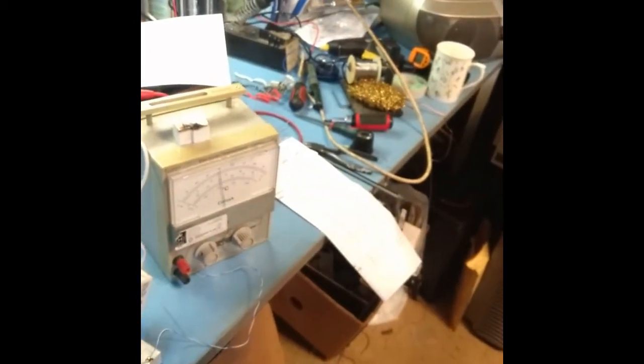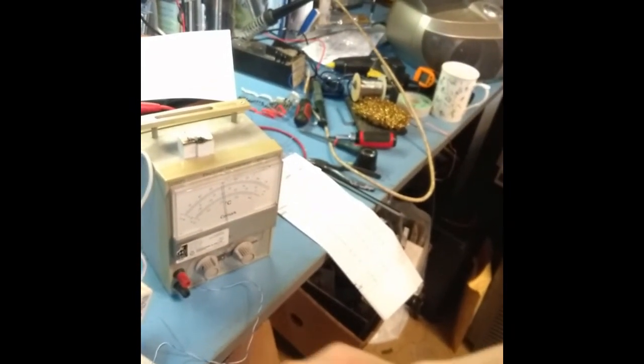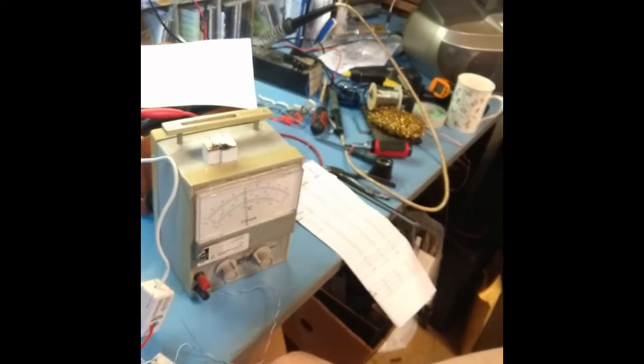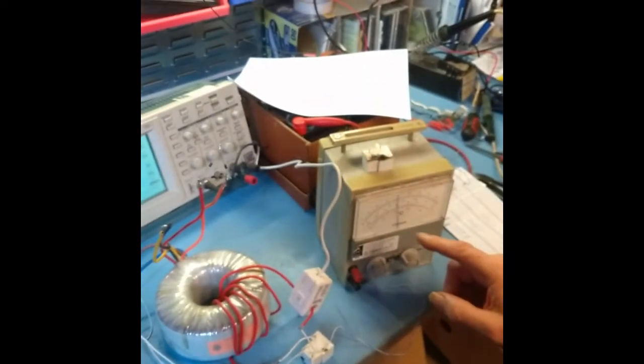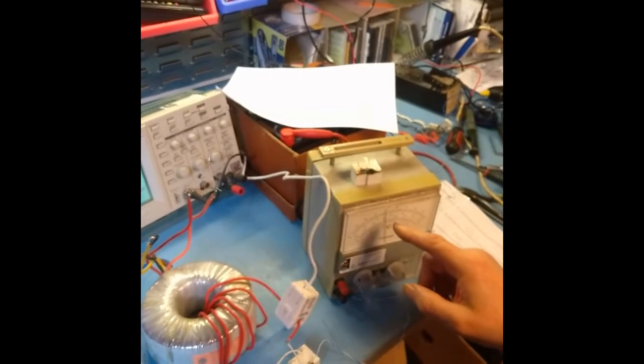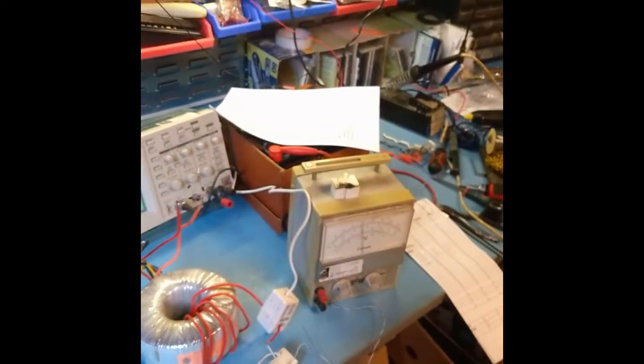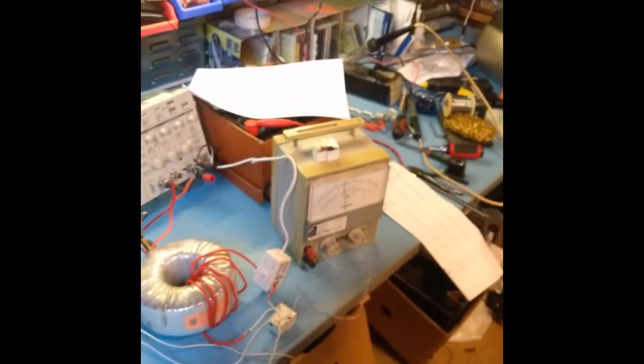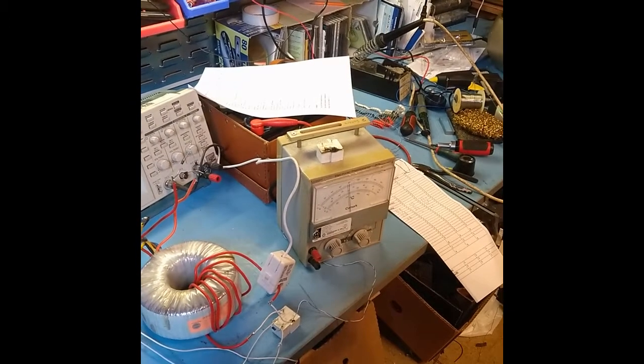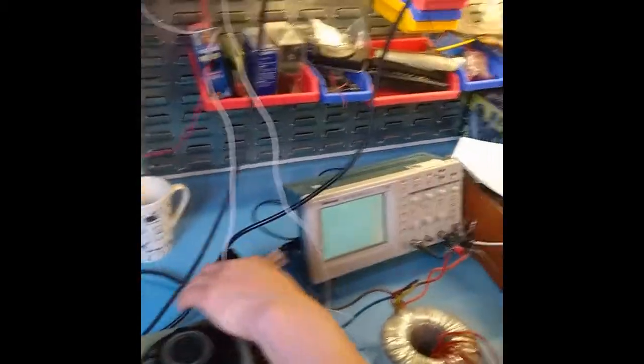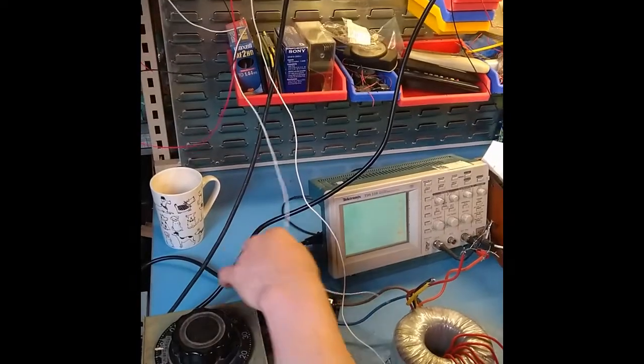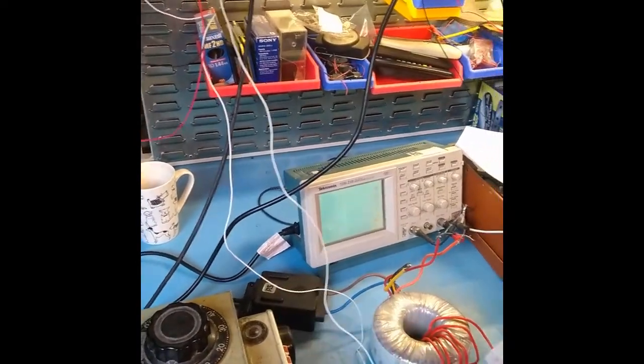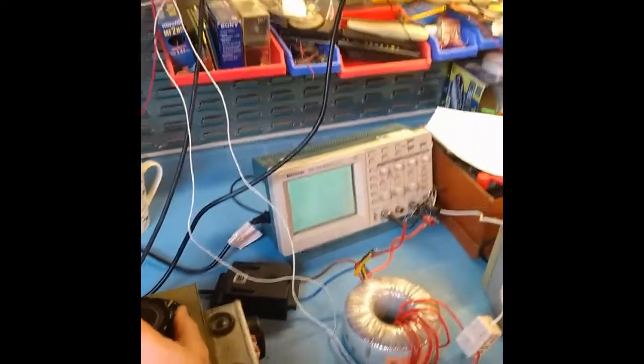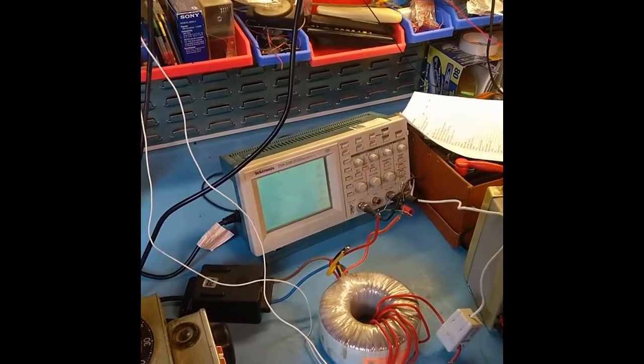So, not surprisingly, we have some heat in the coil even at 0 current. The heat from the coil is warming the relay. The contact pin is at 25.5 degrees centigrade, and near 26 degrees centigrade. I'm now going to start putting some current. So variac to 0, close the circuit breaker. I know it's not really a circuit breaker, it's something else.